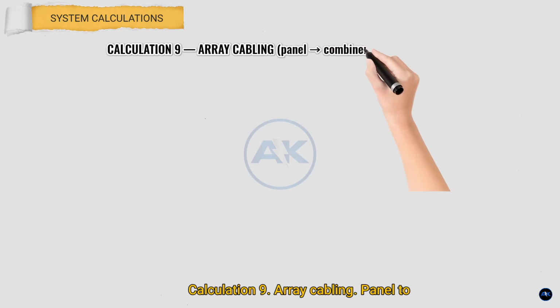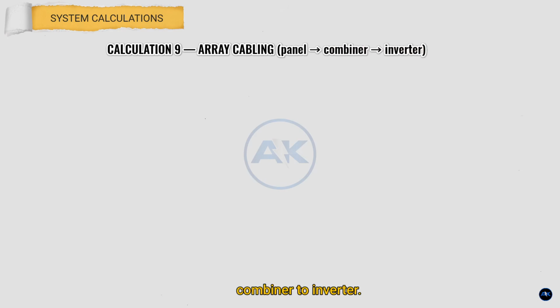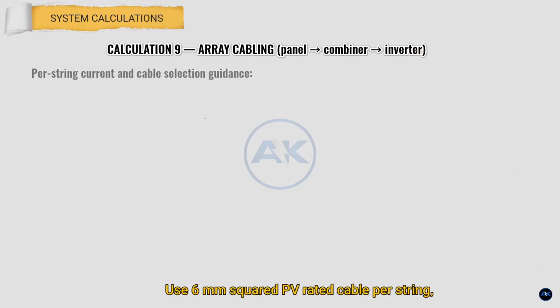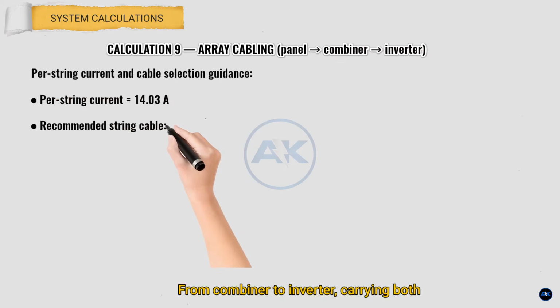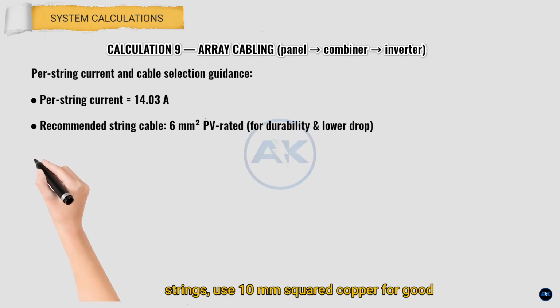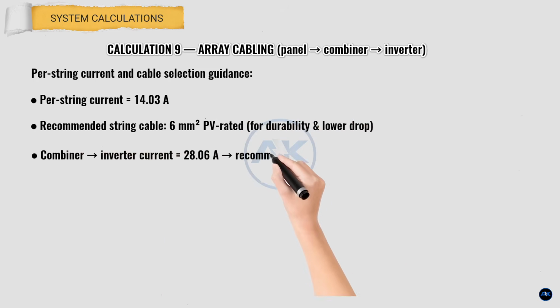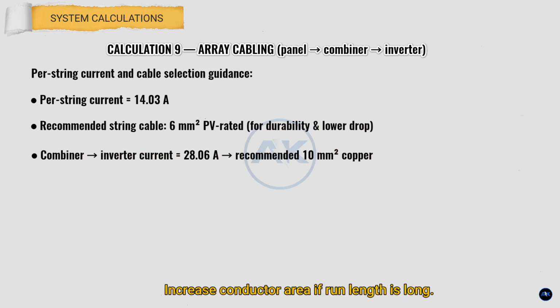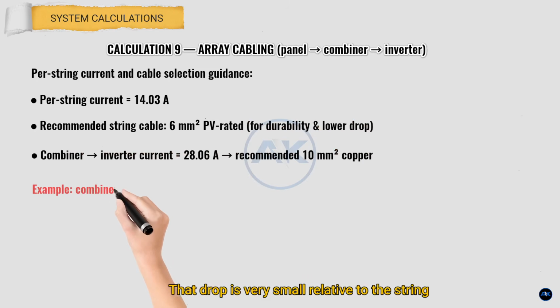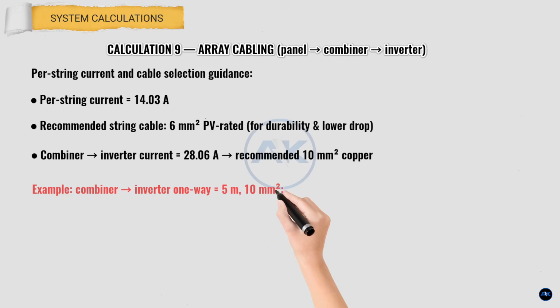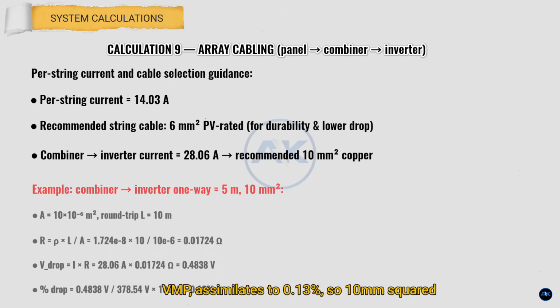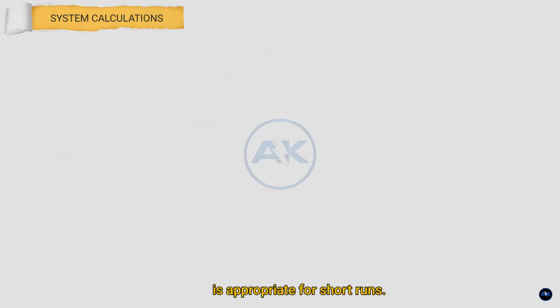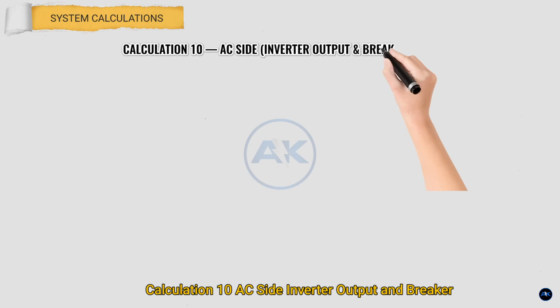Calculation 9. Array cabling, panel to combiner to inverter. Use 6 millimeter squared PV-rated cable per string, panel to combiner. From combiner to inverter, carrying both strings, use 10 millimeter squared copper for good practice. Increase conductor area if run length is long. That drop is very small relative to the string VMP, approximately 0.13%, so 10 millimeter squared is appropriate for short runs.